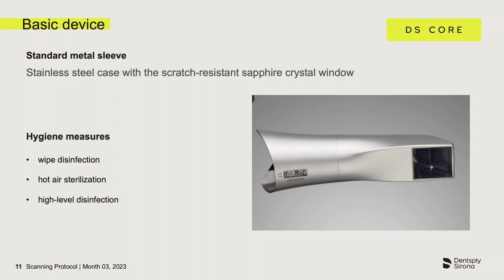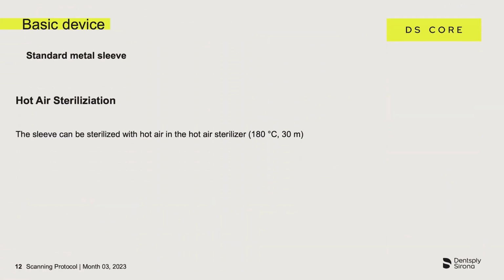It can be prepared with a wipe disinfection, hot air sterilization, or high-level disinfection. The procedure for hot air sterilization is as follows. Number 1. First, a pre-cleaning is carried out. Number 2. Secondly, a removal of the sleeve from the scanner body.